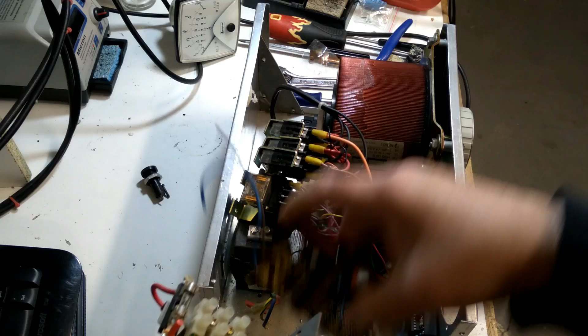And I had a fuse in the front to protect the first winding, which was for the 0.5 amp scale, the 500 milliamp scale. The reason I did that is because I used a small gauge wire to be able to wind all these windings on the current transformer, because I couldn't fit it otherwise - so I used a smaller wire because it was for the smaller scale.